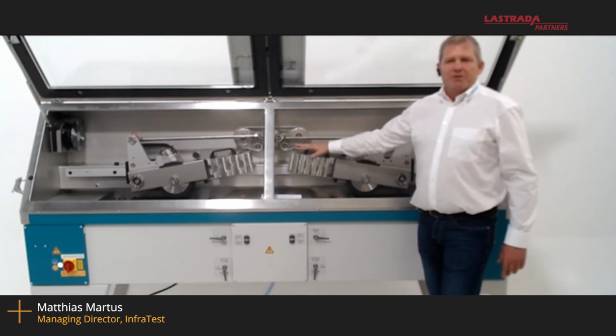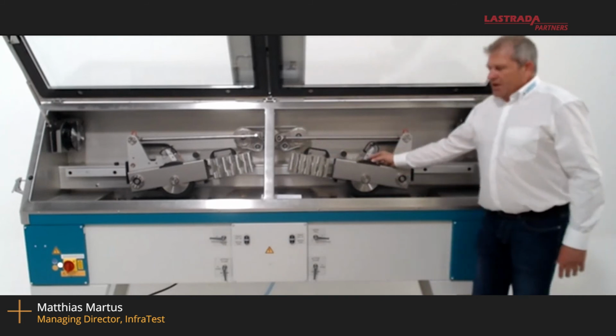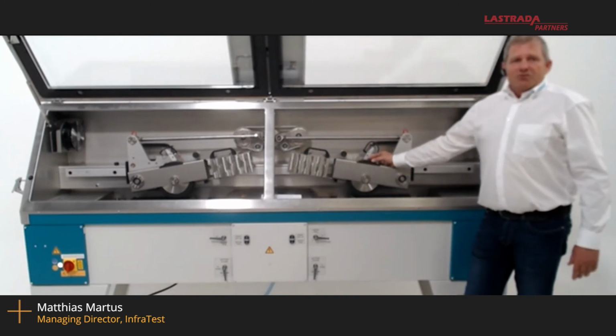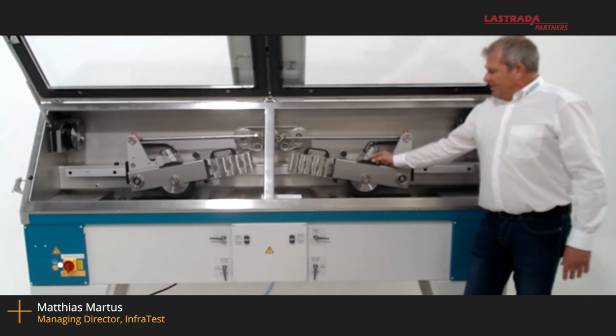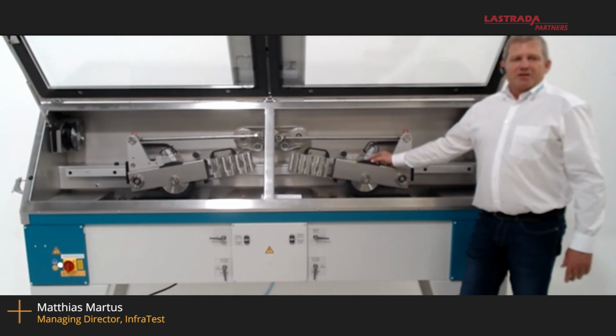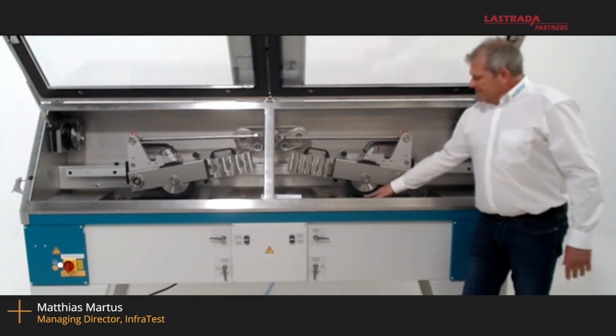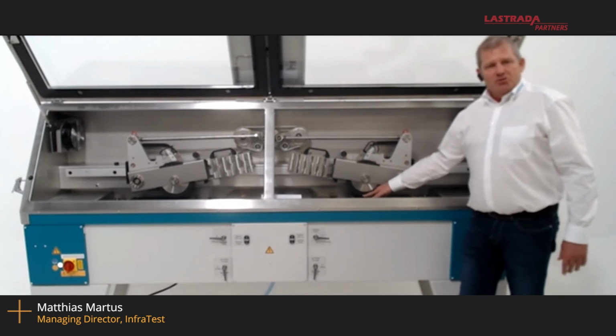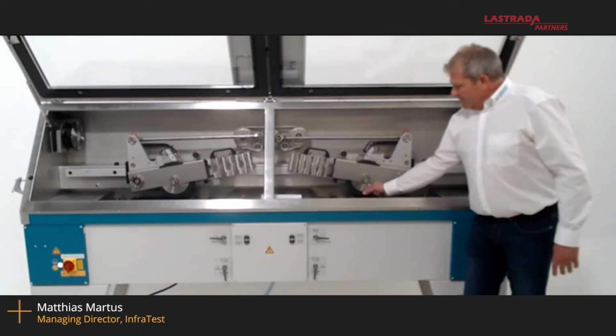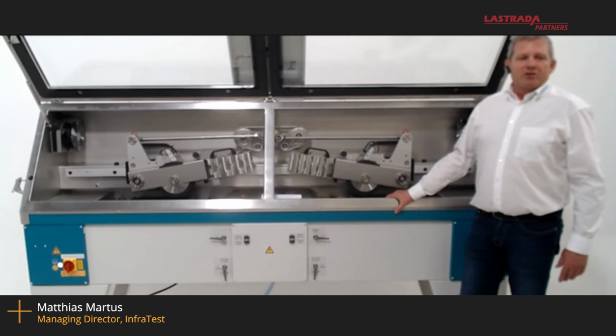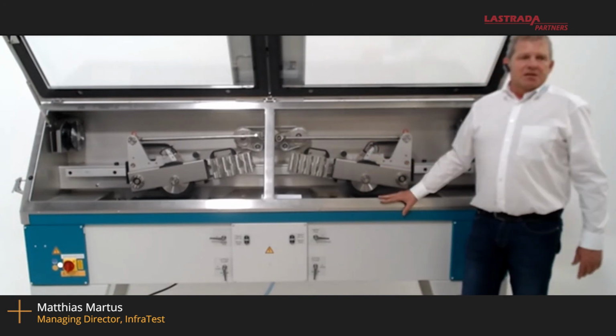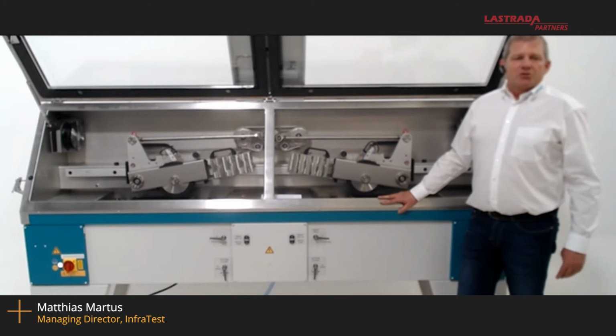So we can simply double the weight, and at the same time we can make the wheels thinner and thinner. We have 50 millimeters at this point. We can have 38 and 25. That means at the end the pressure on the gap is also increased, because the moving wheel is smaller on the sample. So you can adjust this machine to every research facility or any research idea you need, in terms of increasing weight, and in terms of different wheels and different geometries on the sample.